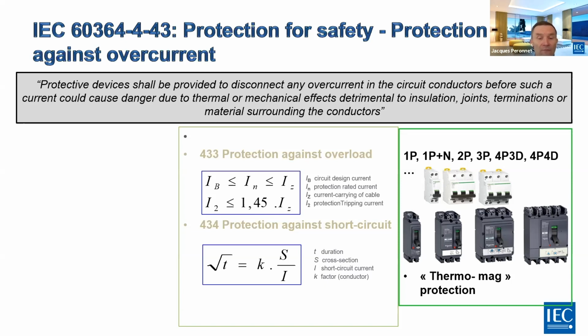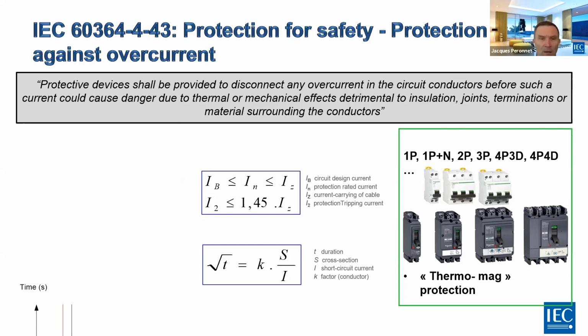And then in clause 434, we are going to deal with the protection against short circuits. There we are going to consider also the duration, which is a key factor in this case. So this is more or less based on this curve that we are going to describe your protection and select the right OCPD, so overcurrent protective device, in order to cover the cable current carrying capacity and the maximum short circuit current that you have to apply.